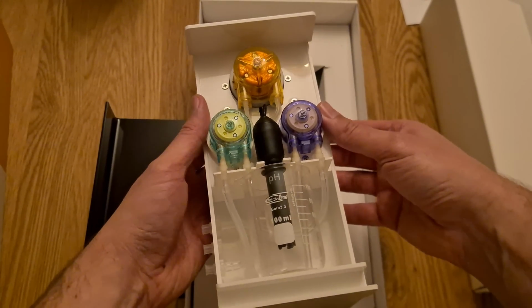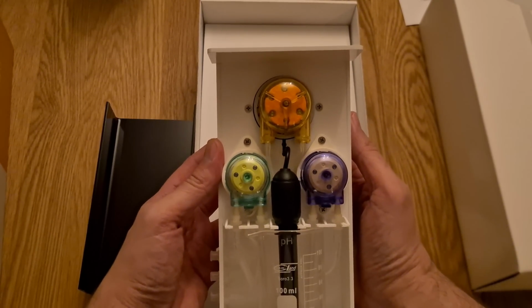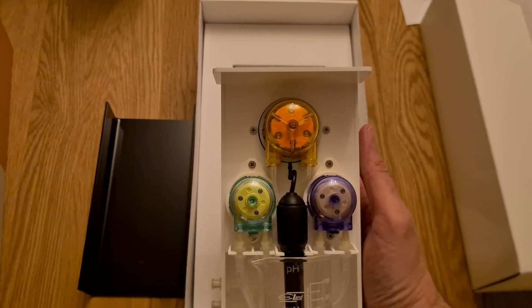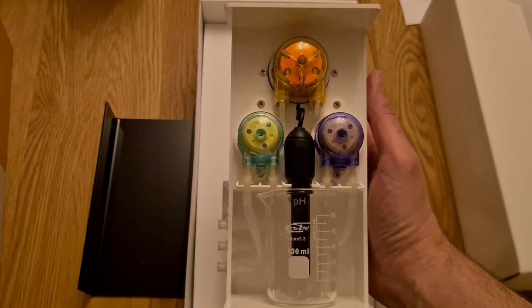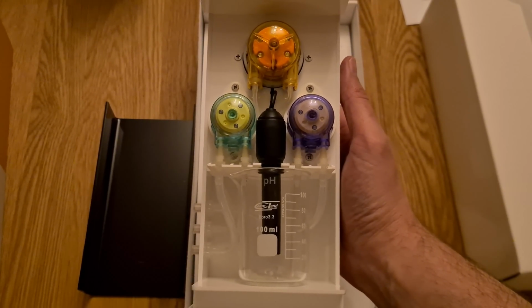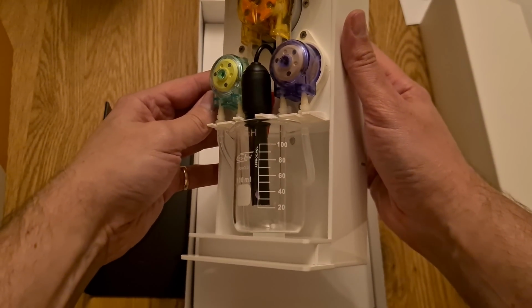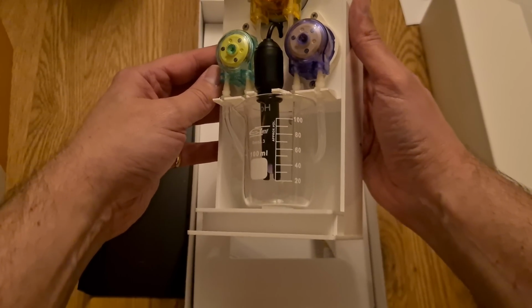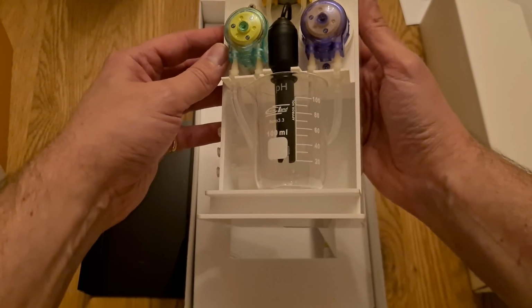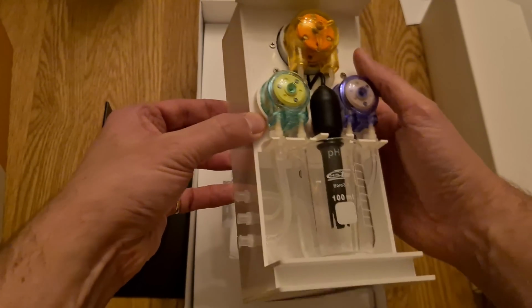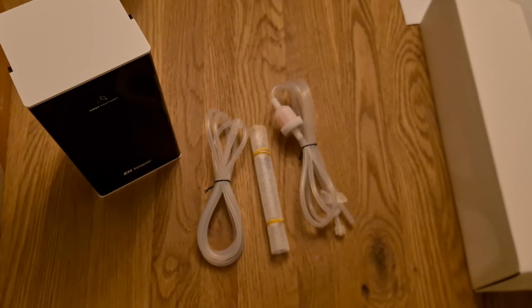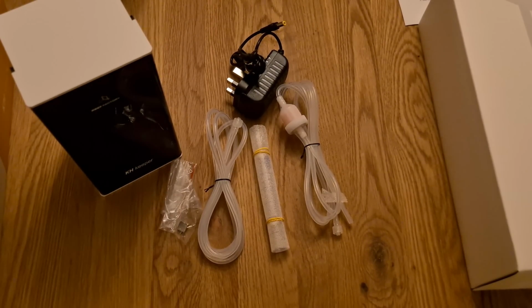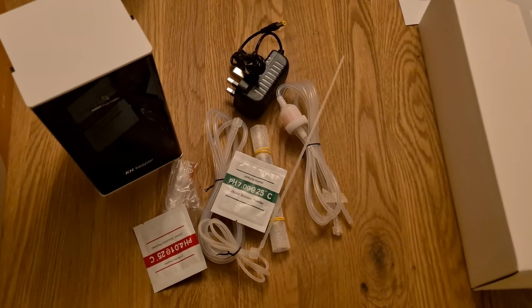The KH Keeper itself has 3 dosing heads, one to draw water from your aquarium to the testing beaker, one that drains the water after the test is complete, and a precise stepper motor to add the reagent to the test sample. In the testing beaker is a small magnetic stirring bead to mix the reagent, and a pH probe to determine your alkalinity test result. Along with the device you get 2 measuring cylinders and pH sachets for calibration, as well as all the tubing you need to set up.